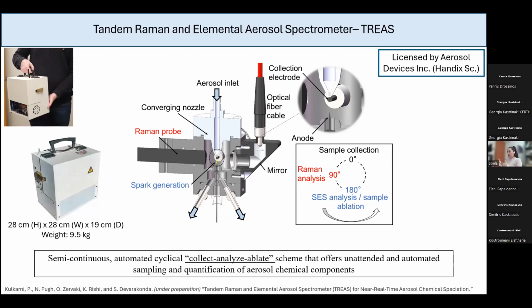After the Raman spectra are acquired, then the electrode rotates again by another 90 degrees, where the sample now faces a sharp electrode. The sharp electrode and the collection electrode form, when you apply high voltage, a spark generation that's burning the sample, and the radiation that is emitted is then collected by an optical fiber cable, which can give you elemental identification of the composition of the sample. This also ablates the whole sample. It cleans the collection electrode, and then it's ready to return to its initial position, where the new cycle of collect, analyze, and ablation begins.